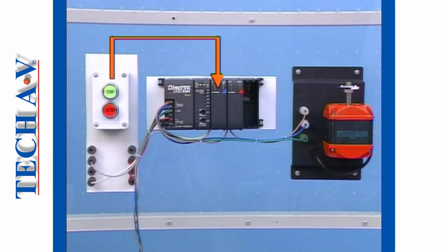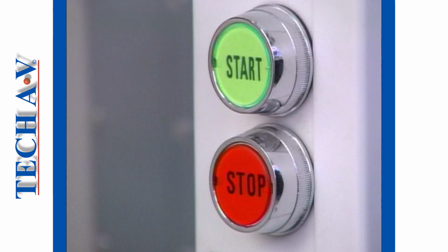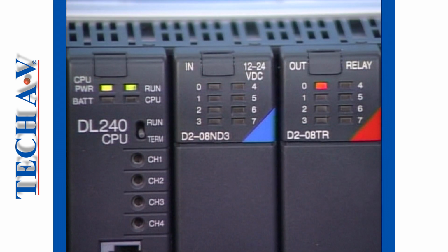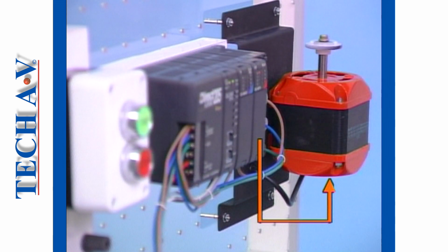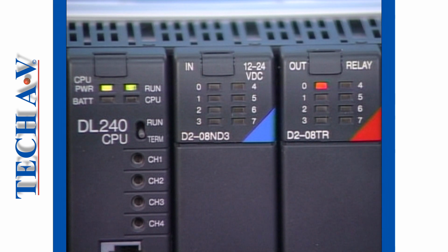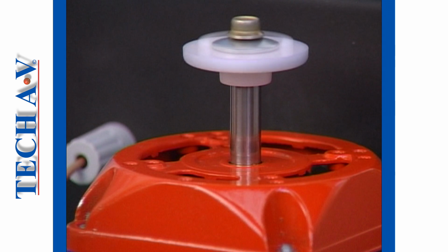The main function of the input interface is to protect the computer circuits within the PLC by electrically isolating and conditioning all incoming input voltage signals to the PLC. Outgoing signals from the controller are processed in a similar way through the output interface circuitry. For example, low voltage output signals are buffered via relays to isolate the PLC when it sends signals to high voltage output devices.